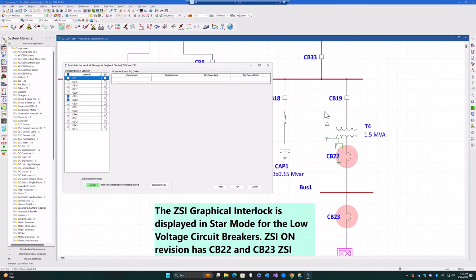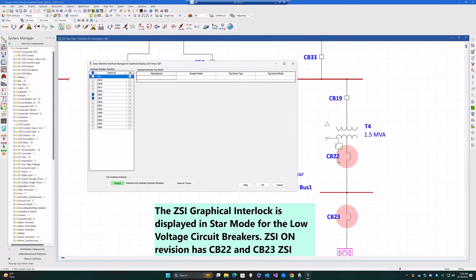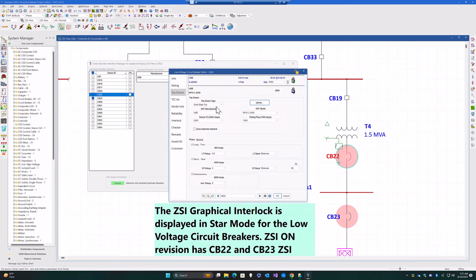And then, so I'll bring up the ZSI manager first from the toolbar on the right hand side, and we can see CB22 and 23 are selected for ZSI wiring, but it's disabled. In fact, we can double check that. You can select CB22. We can see it's an ABB breaker, and this one's a Cutler Hammer. And you can double click on CB22 to open up the editor, and you can see ZSI is actually deactivated or not selected in this particular revision.